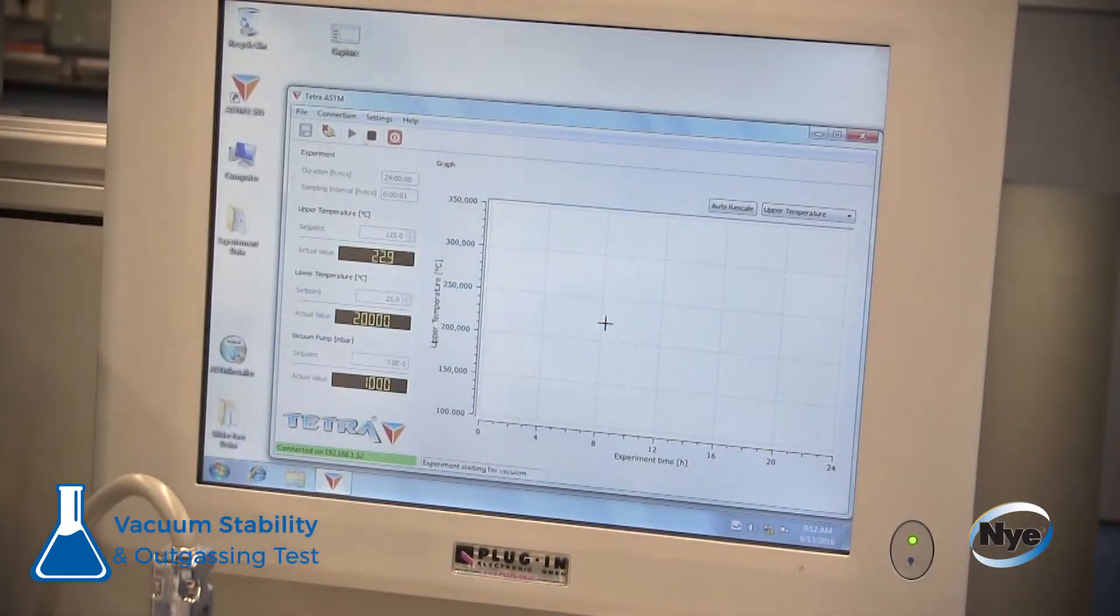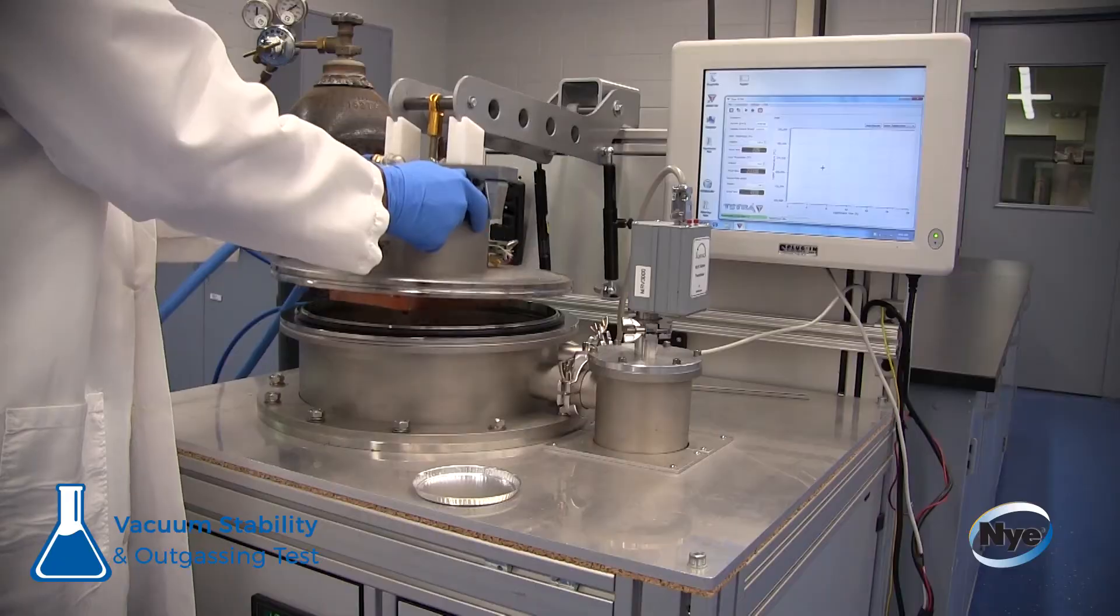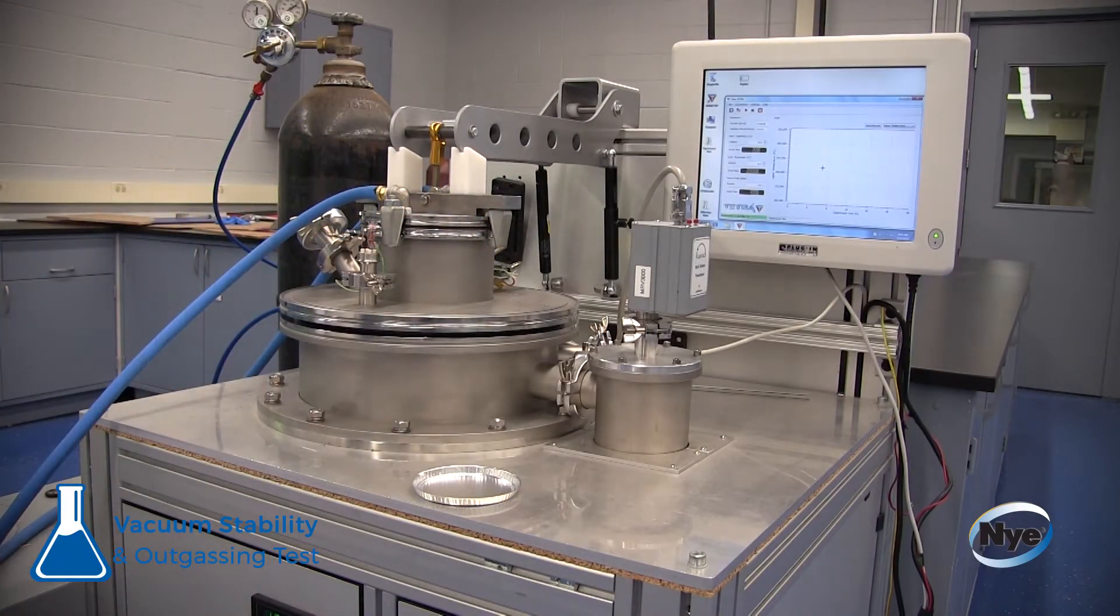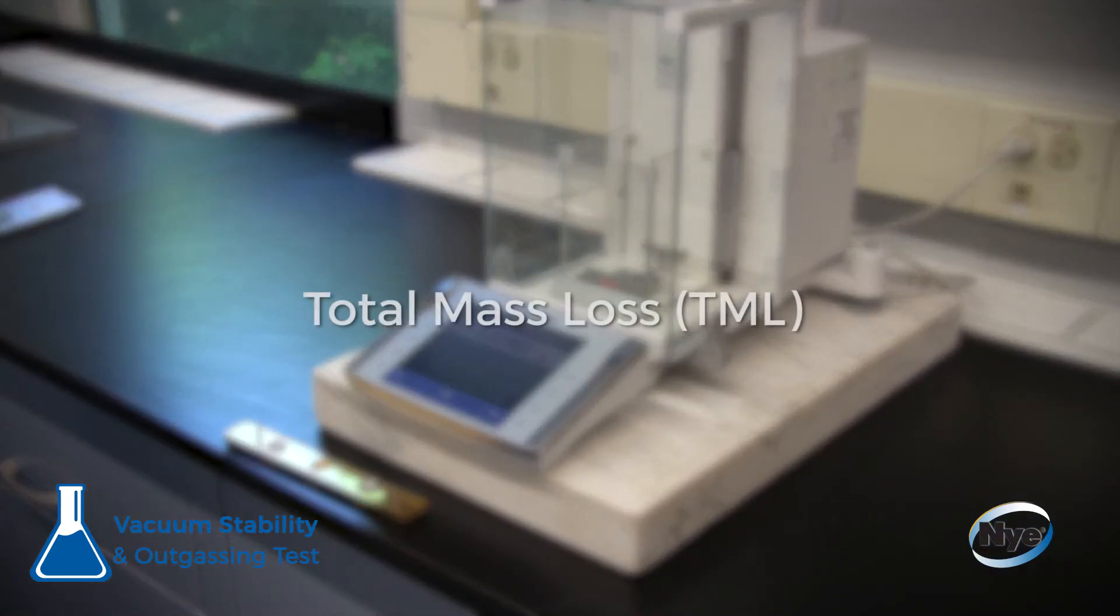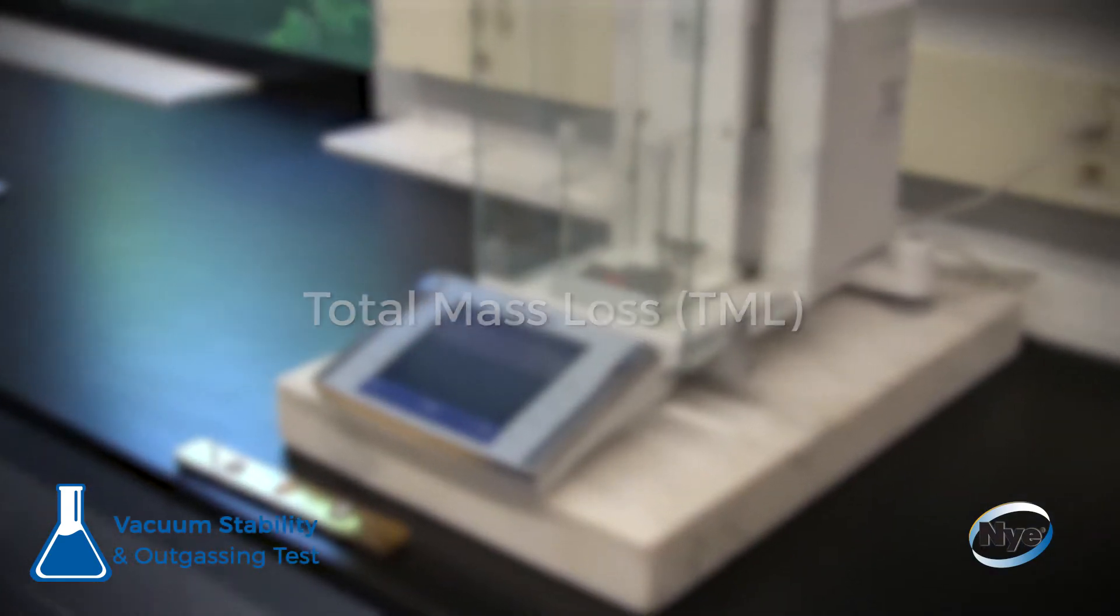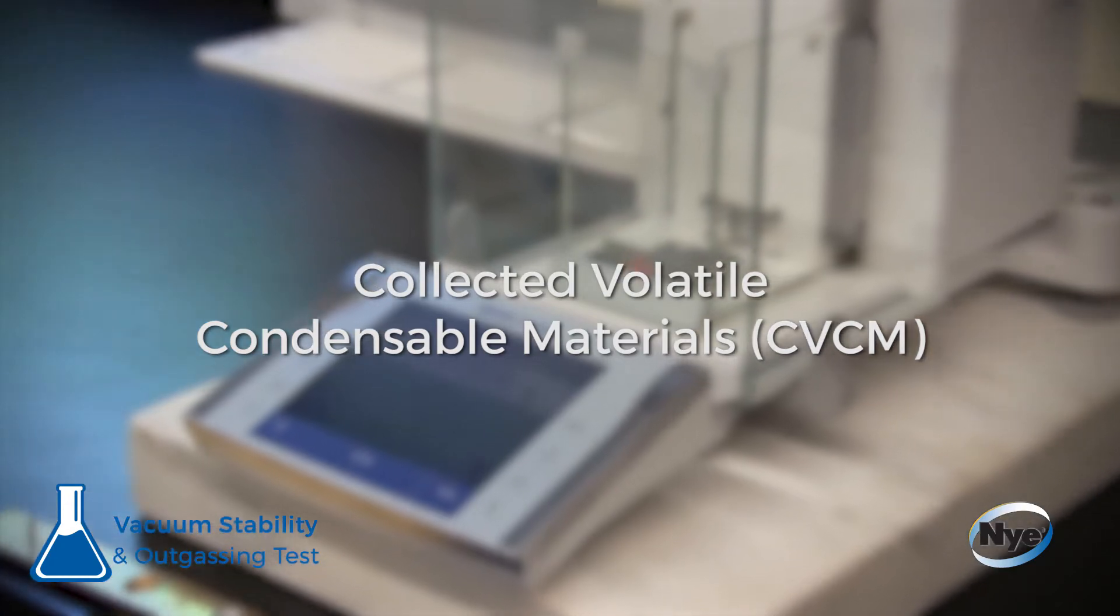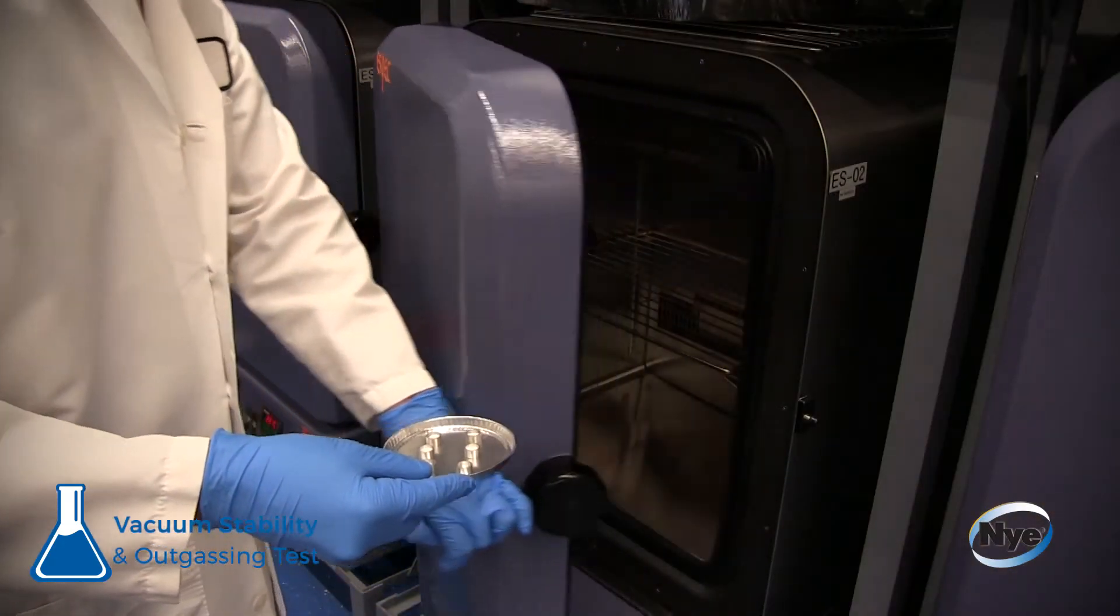The purpose of the test is to determine the amount of volatile content in a material when exposed to heat and vacuum in a closed system. The two parameters that are measured are total mass loss and collected volatile condensable materials.